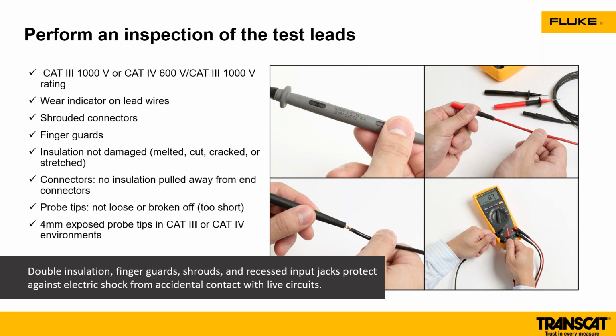Let's talk about your test leads, because again, this is an extension of your PPE. Make sure that your test leads are rated appropriately. Do a physical check on them. Make sure they're not wearing down, because if you're touching 480 volt and you have a nick in your test lead, that could potentially touch you to cause a fault or some type of incident.